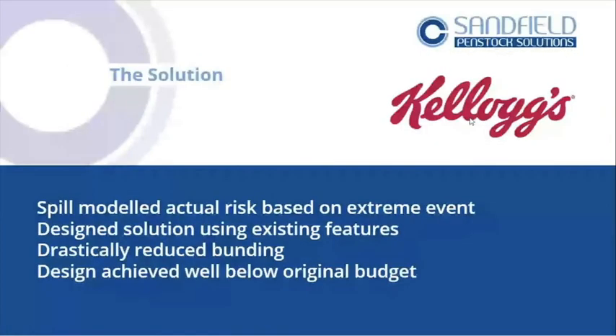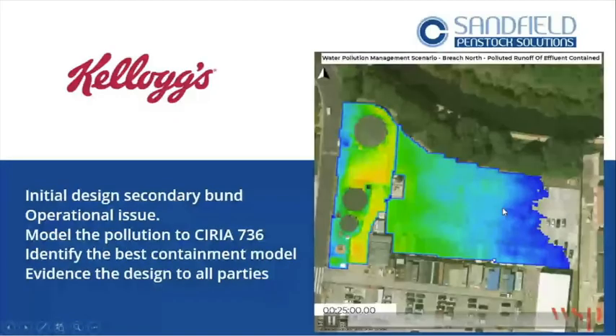This gave the engineering department something to present to management. The solution was to spill-model the actual risk based on extreme events and design a solution using different features. They have an effluent treatment discharge, which gives a maximum rate they can discharge at — a lot of this material could be discharged through that with no issue from the water company. The aim was to drastically reduce the bunding, stop building a brand-new structure when it wasn't needed, and achieve a design using existing assets within a reasonable budget.